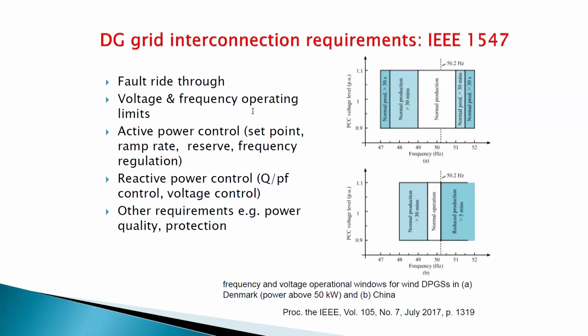Voltage and frequency operating limits. As we know, the nominal frequency is 50 hertz. So how much deviation can we afford to have? Not much, like frequency 49 to 51 hertz. In the same way, how much variation is permissible for voltage? Plus minus 10% in the transmission system, and in the distribution system, plus minus 5%. Then, as I mentioned, we have to keep the power balance in generation and consumption, both for active power and reactive power. A little bit of imbalance is permissible, but not much.